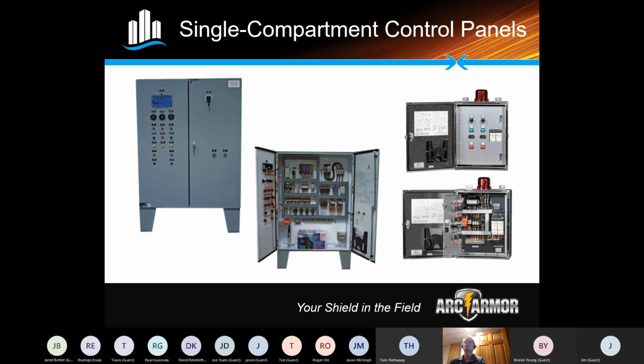All right, moving on. This is just a slide. I know it says single compartment. We've got a couple of two-door enclosures, but these are just different types of control panels that you can see out there. There are different flavors and looks, including panels that are on legs. Normally the legs are there to give the air gap required by each state. Normally it's 18 inches, some have 24 inches. That gives the required air gap if it's installed right over, say, a wet well, so you have the ability to off-gas anything coming up prior to entering the control panel. And sometimes you will see skirting across those.